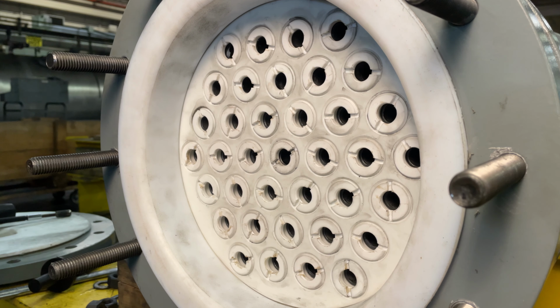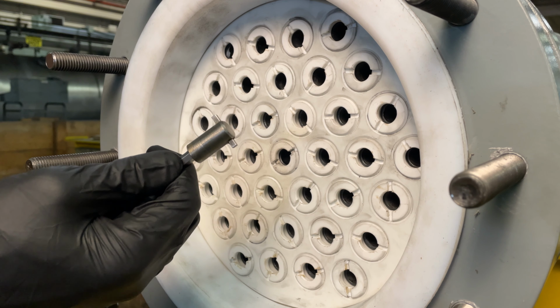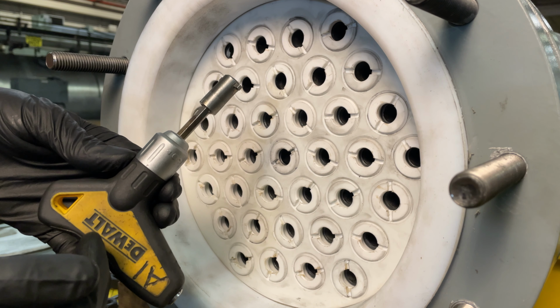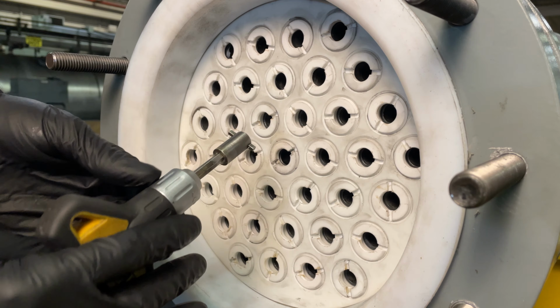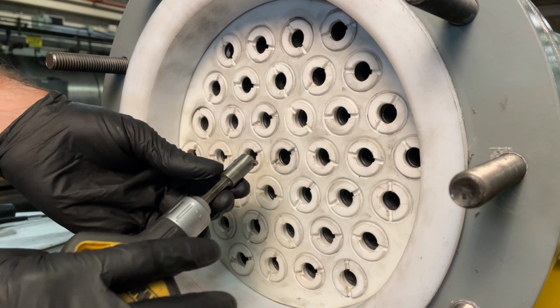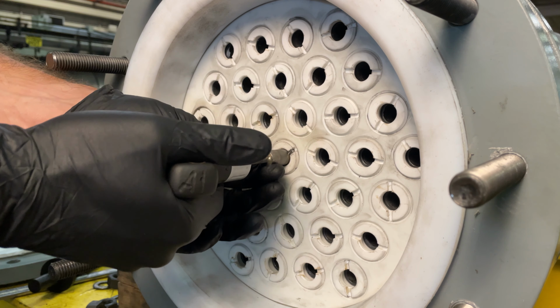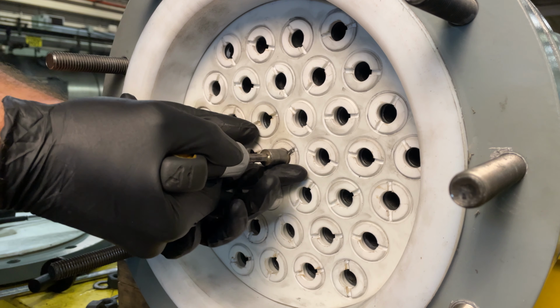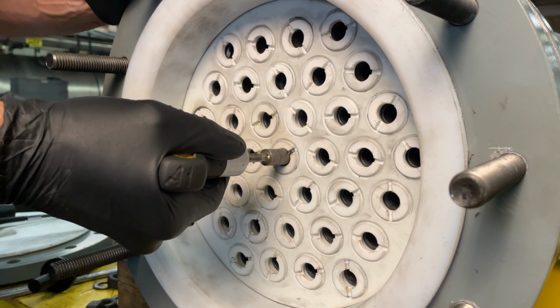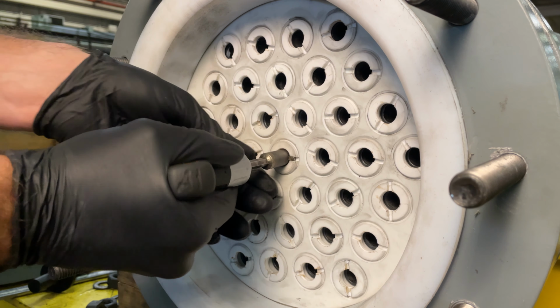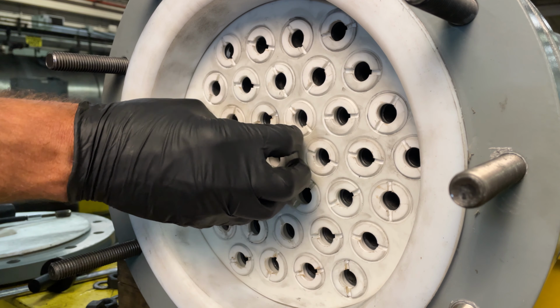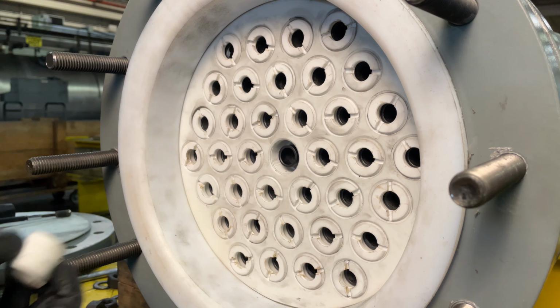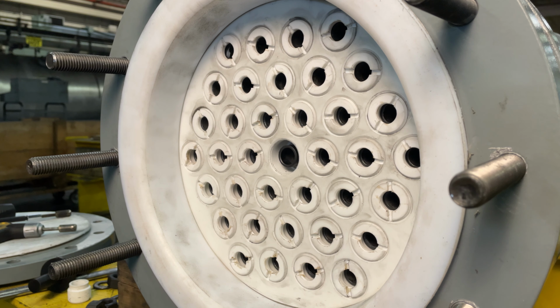Once you've identified the tube that needs to be replaced, take your tube nut bit in your ratcheting T-handle or other appropriate tool and place the tube nut bit into the face of the tube nut. Apply forward pressure so as not to strip out the tube nut face as you begin to unscrew the tube nut. Once the tube nut is removed on one tube sheet, you will have to remove the tube nut on the opposite tube sheet for the corresponding tube. At that point, you'll be able to push the tube out from the opposite side.